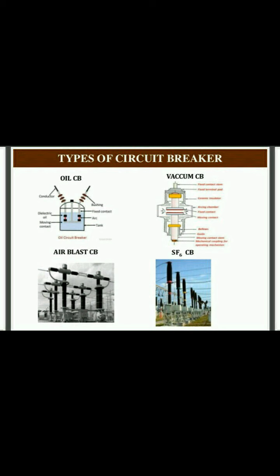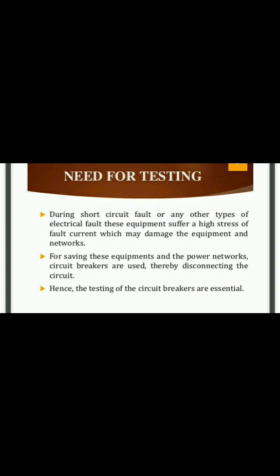The need for testing of a circuit breaker is a very important part. During a short circuit fault or any other type of electrical fault, the equipment suffers high stress from fault current, which may damage the equipment and networks. For saving the equipment and the power networks, circuit breakers are used, thereby disconnecting the circuit. Hence, the testing of a circuit breaker is a very important thing in electrical engineering, and the basic need of a circuit breaker is for the security of an electrical power system.